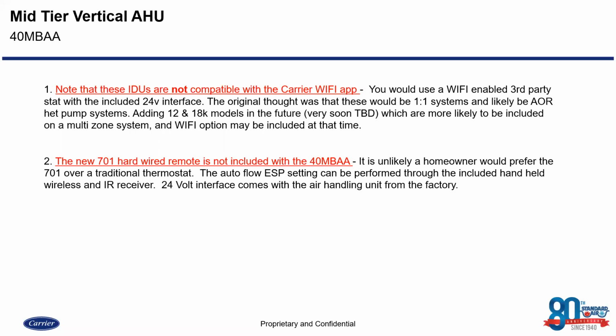The wired controller, which in this case, if it was compatible with a ductless wired controller, which would be the KSACN 0701, is not included, nor is it compatible with the 40 MBAA. And that ultimately stems back to the same reason that we're dealing with the lack of compatibility for Wi-Fi, because the whole idea of this was to be a residential replacement, something that we could replace a residential furnace and still use the customer's thermostat that they're familiar with, whether that be Honeywell, whether that be Ecobee, whether that be Nest, or whatever that they're asking for, that we can integrate that into the ductless system for seamless control.